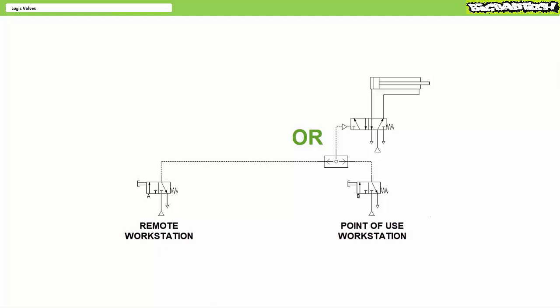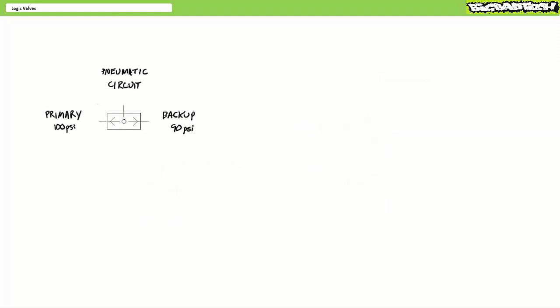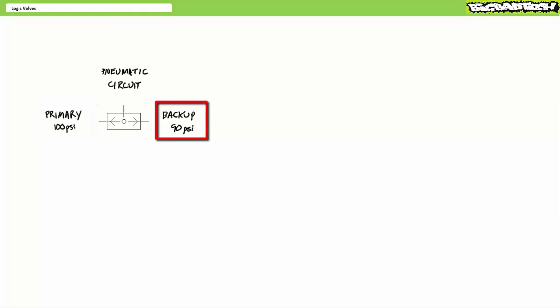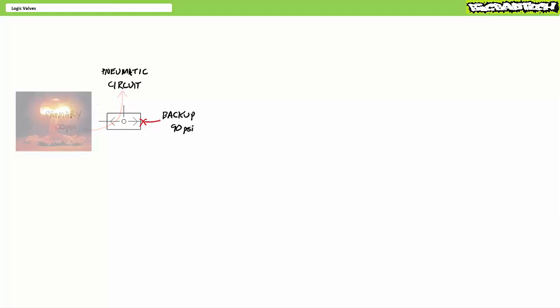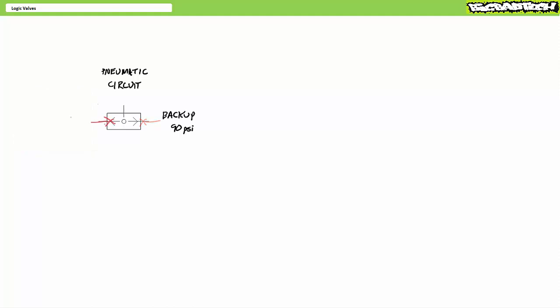Beyond logical operations, I'd like to highlight the pressure selection feature of the OR valve. This is a handy feature commonly employed in pneumatic systems necessitating a backup or alternative source. Consider a primary pneumatic source operating at 100 PSI and a backup accumulator charged at 90 PSI as inputs to an OR valve supplying a pneumatic system performing a critical operation. In ordinary circumstances, the OR valve passes the primary source at 100 PSI to the system. In the event of failure of the primary source, the OR valve passes the backup accumulator to the pneumatic system, allowing time for an orderly shutdown.